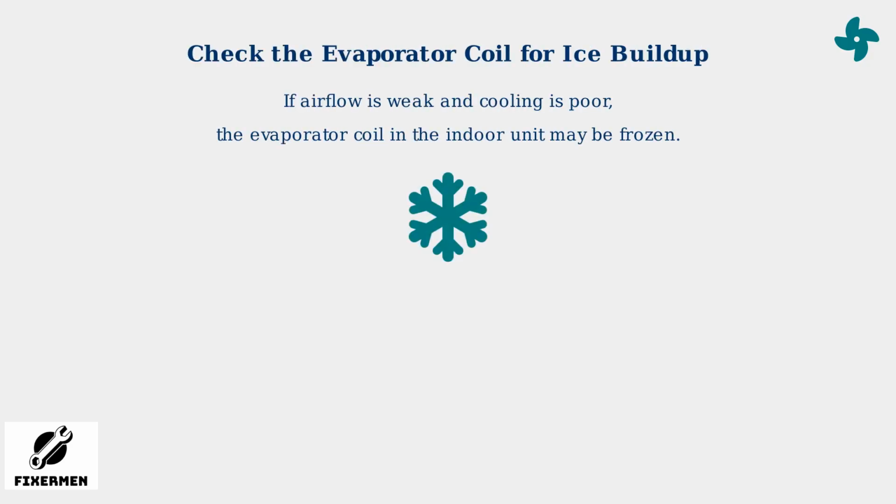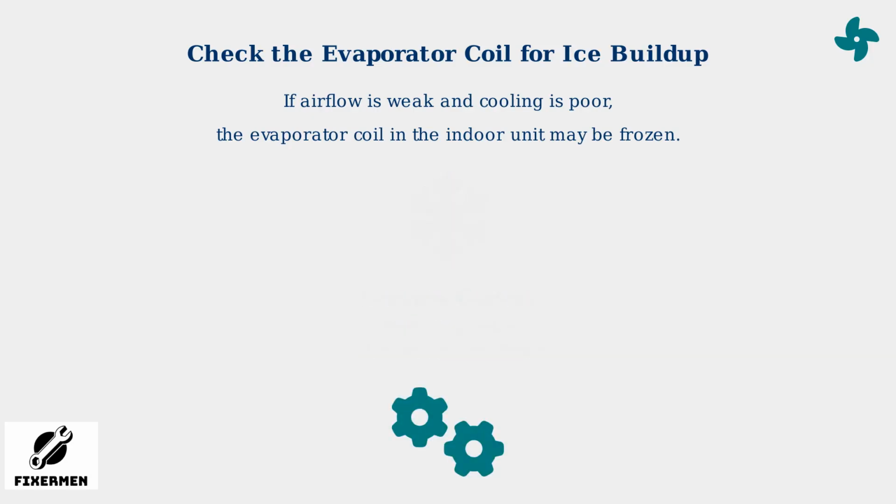If you notice weak airflow and the air conditioner isn't cooling effectively, the evaporator coil inside the indoor unit might be frozen. This commonly happens due to restricted airflow or low refrigerant levels. Common causes include blocked air filters that restrict airflow or insufficient refrigerant in the system.